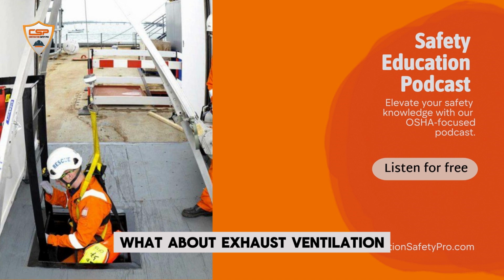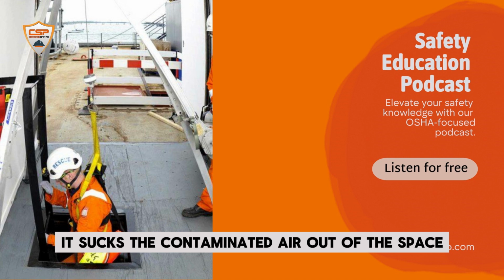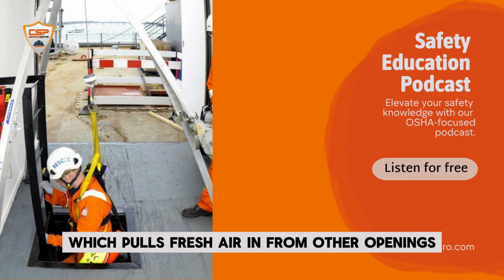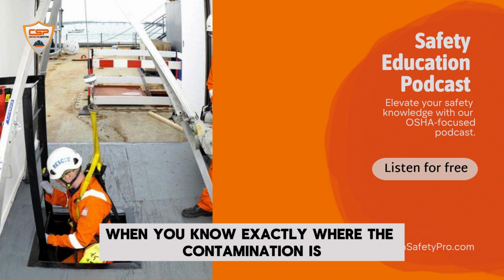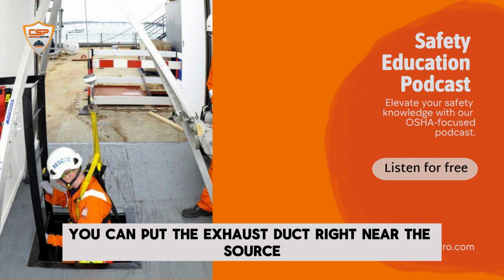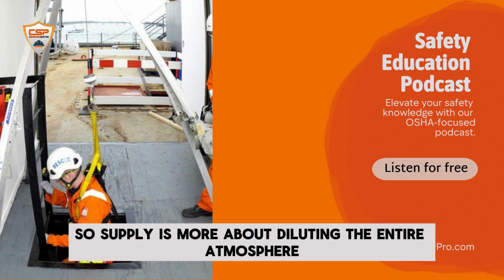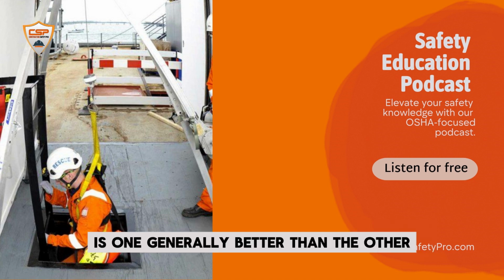What about exhaust ventilation? Exhaust ventilation does the opposite. It sucks the contaminated air out of the space. This creates negative pressure, which pulls fresh air in from other openings. Exhaust ventilation works really well when you know exactly where the contamination is coming from, like if you're doing welding in a specific spot. You can put the exhaust duct right near the source to capture those fumes. So supply is more about diluting the entire atmosphere, and exhaust is more targeted. Is one generally better than the other?